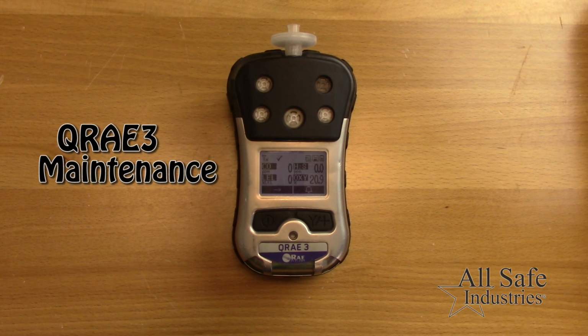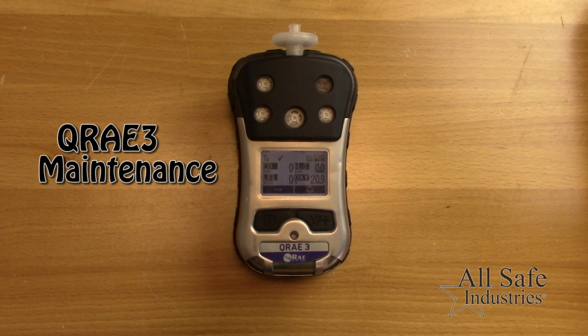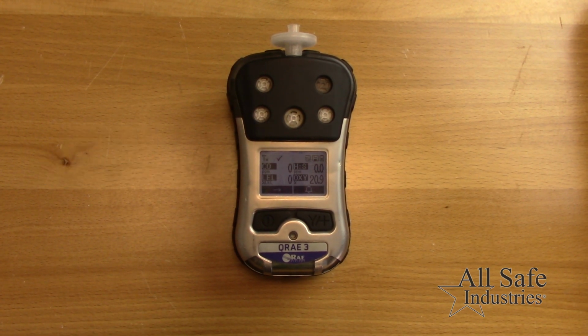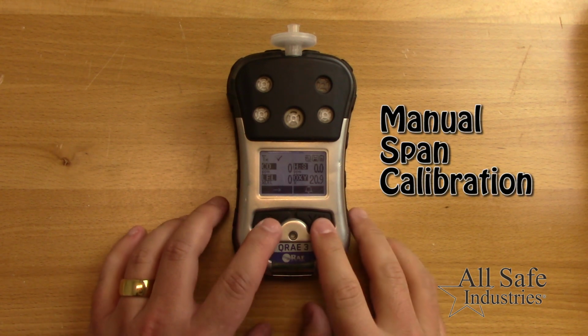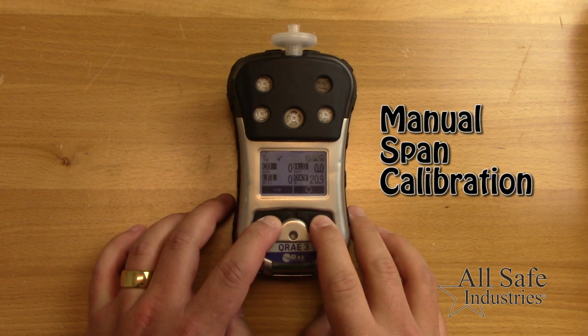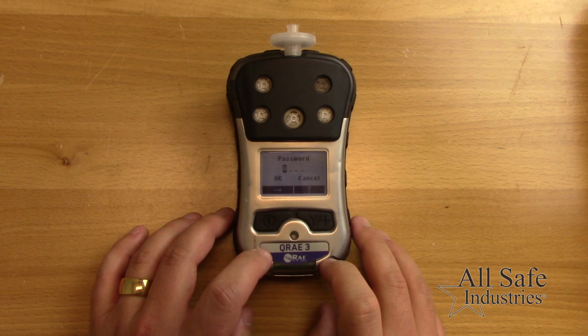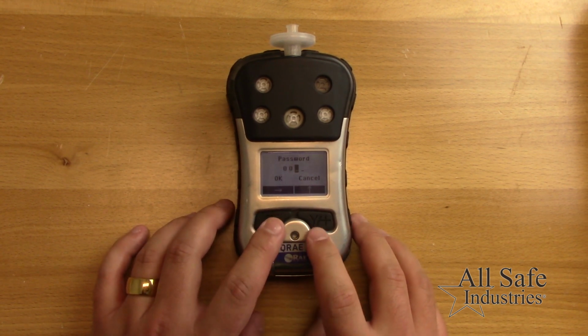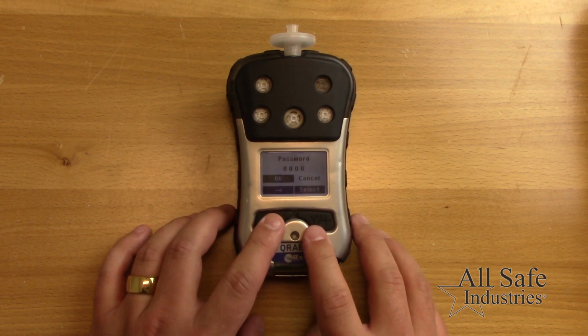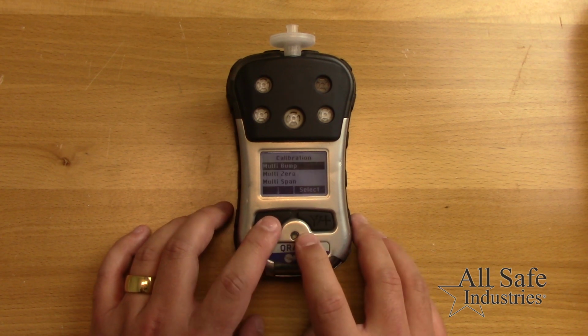This quick video will show you basic maintenance for the QRAE3. To perform a calibration, press and hold both buttons to access the menus. Enter the 4-digit password of 0000 and select OK. Select the calibration menu and then select the multi-span sub-menu.